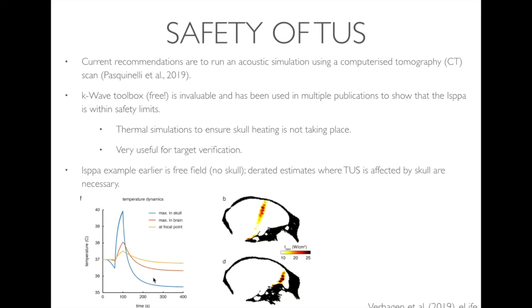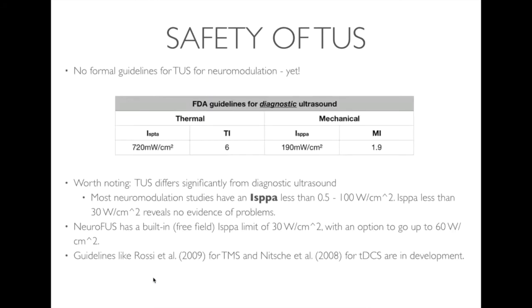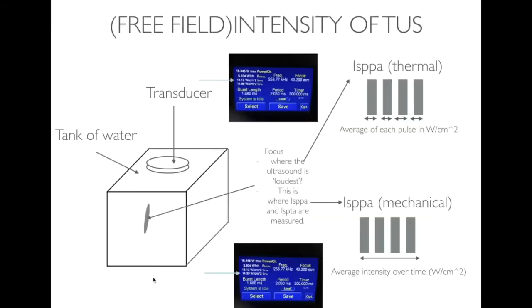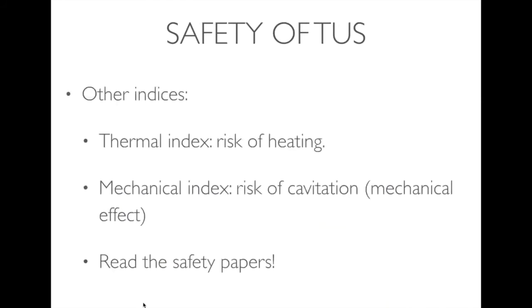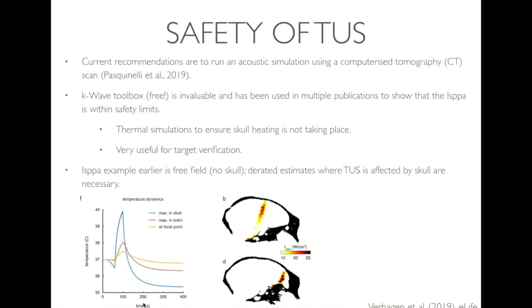It's also worth pointing out that the things I was talking about earlier are called a free field estimate, meaning nothing is obstructing the passage of the ultrasound through the water. Whereas in real life, the ultrasound tends to be derated in some way by the skull. The NeuroFUS system can estimate the free field ISPPA as standard on the touchscreen, but if you want the derated estimate, that relies on you doing some form of acoustic simulation.